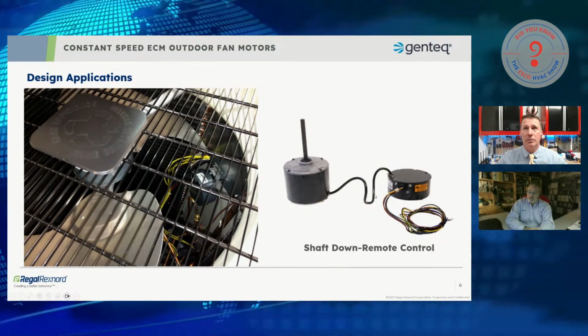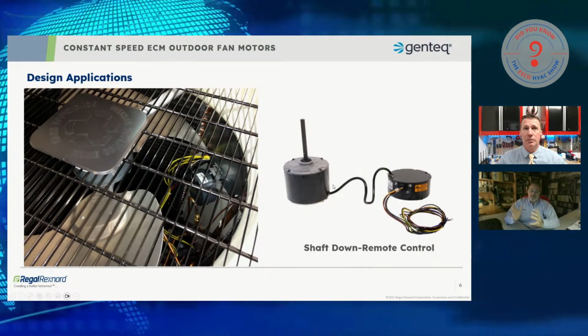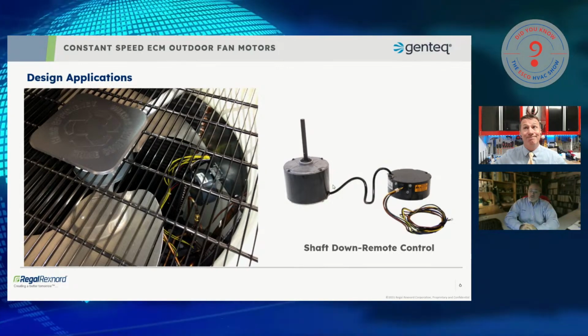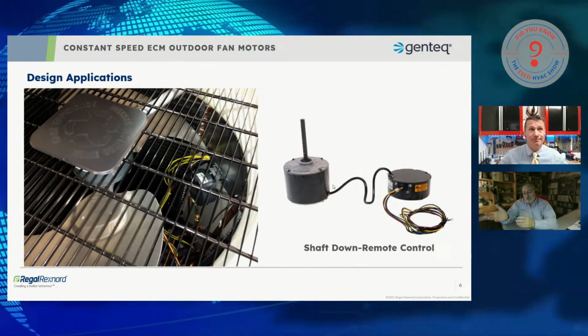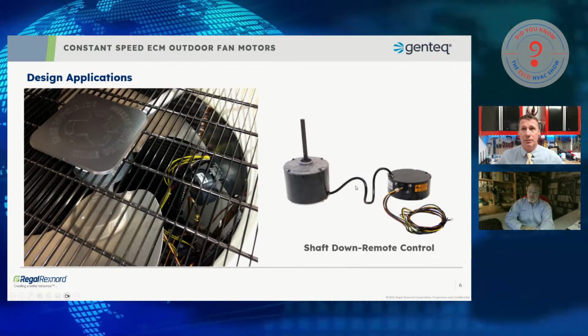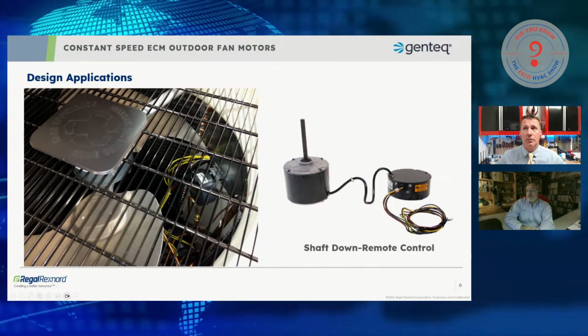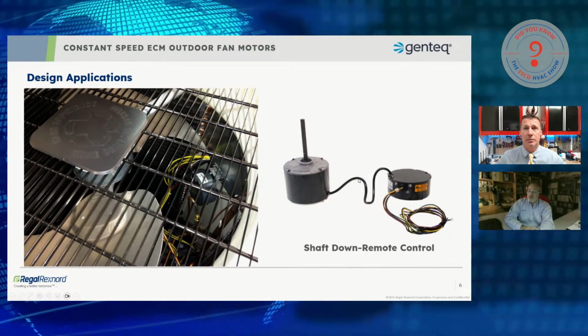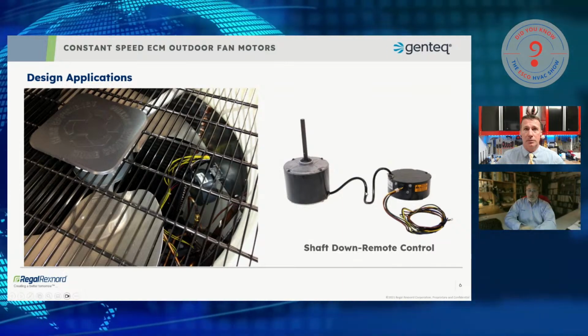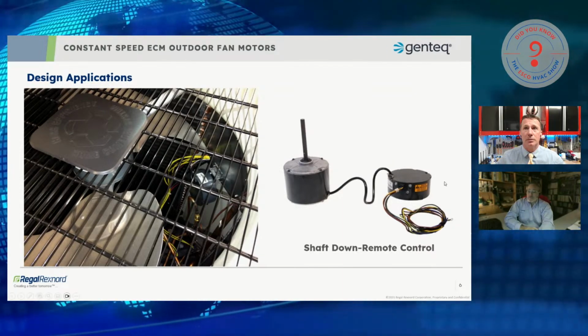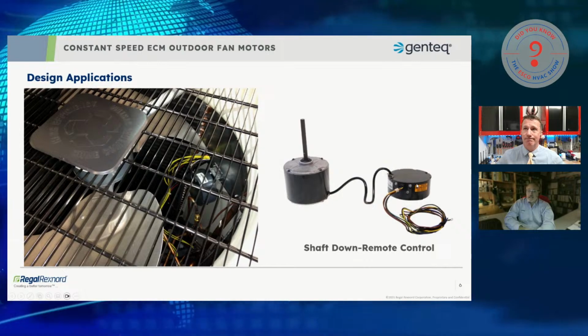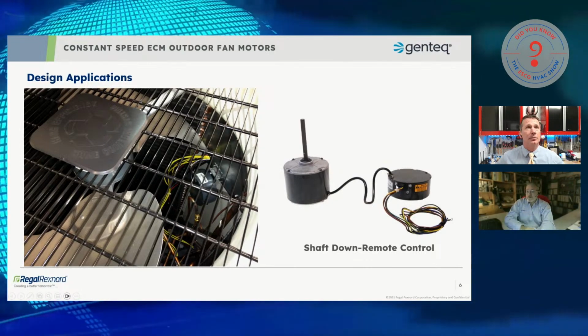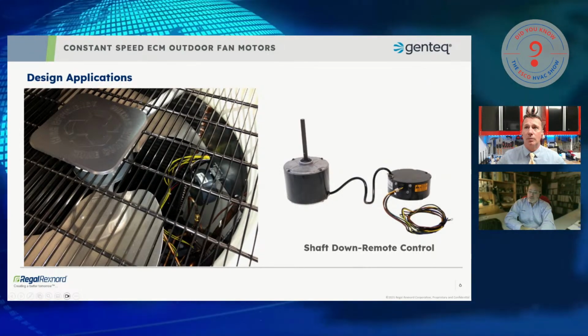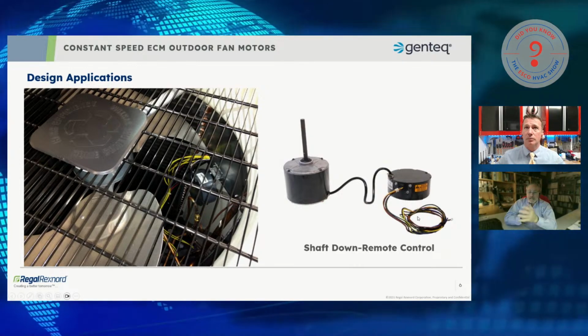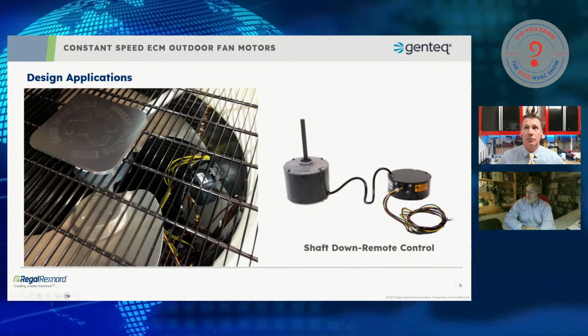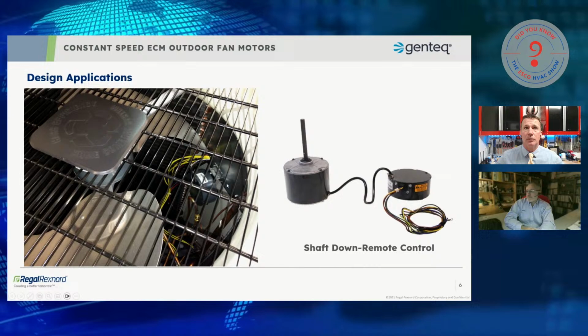So this is that umbilical cord that, again, if you've never seen a remote located outdoor fan motor, or you've never seen a remote located indoor blower motor, is always hidden between the motor and the control. In this case, it's a longer umbilical cord. It's shielded because there is electromagnetic interference that travels through those wires. We don't want that to interfere with anything in the house or around, or them to interfere with the motor. And then we've got the wires that we would normally see connected to the contactor, the circuit board, coming out of the control, and those go into the control panel.